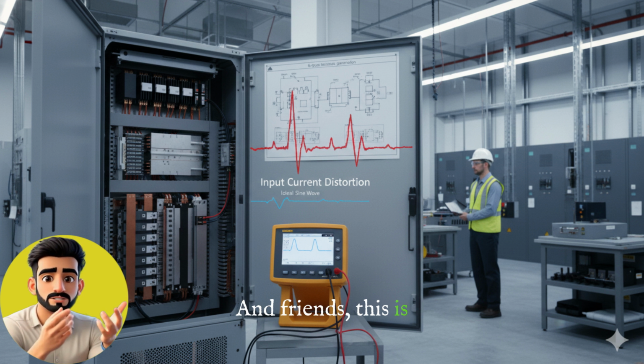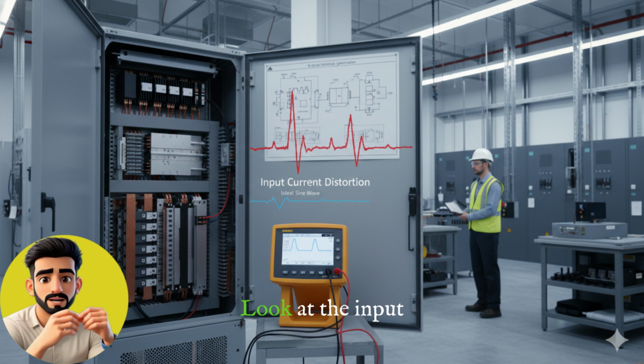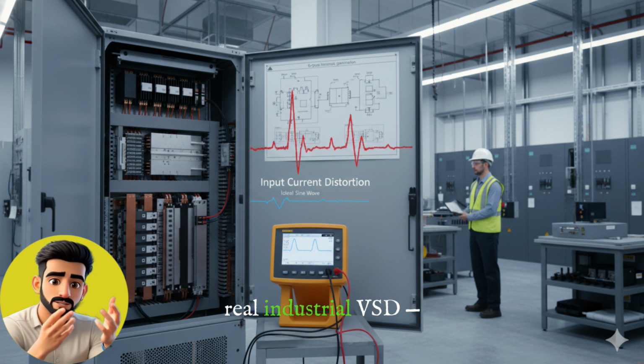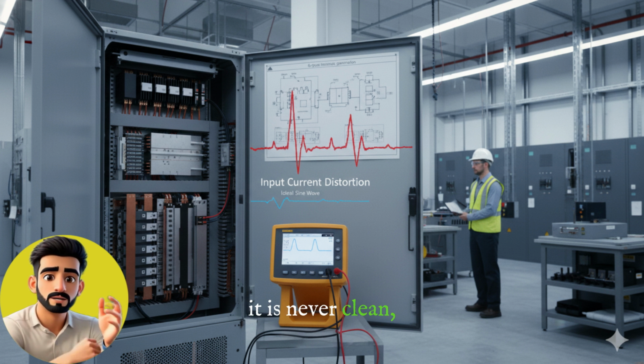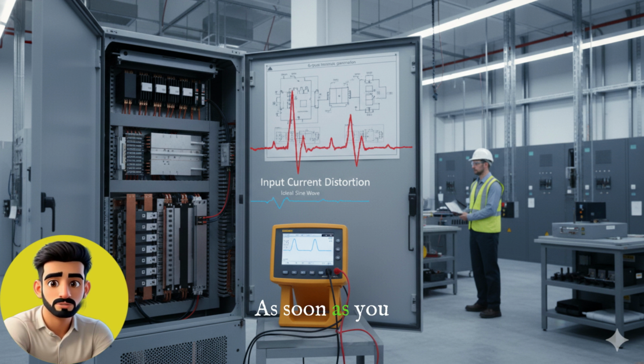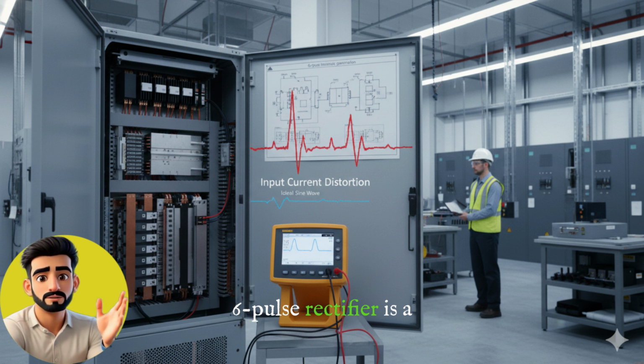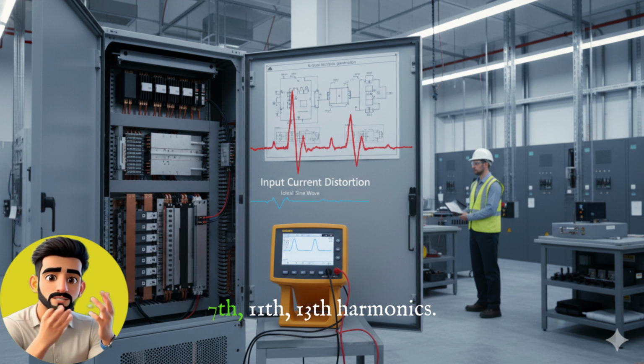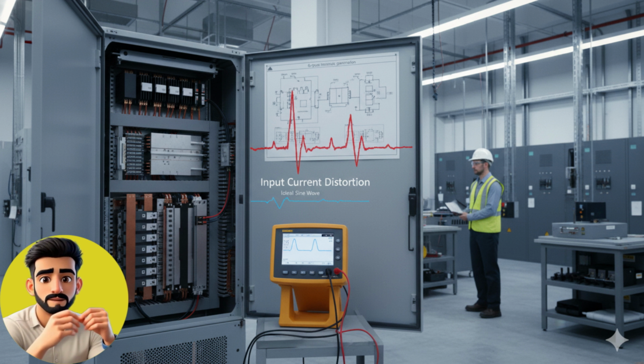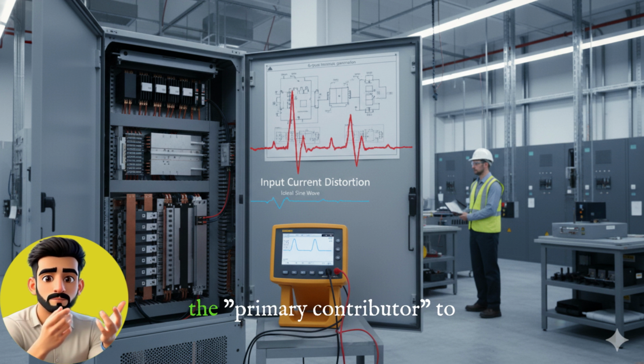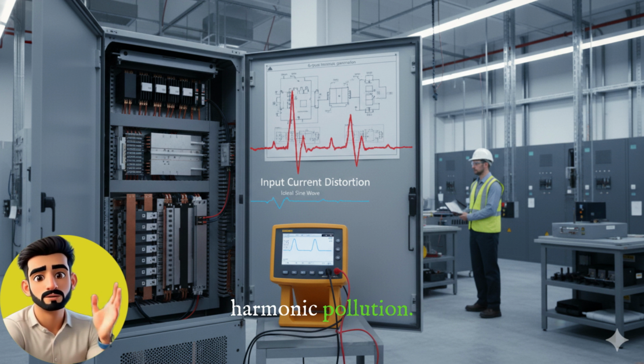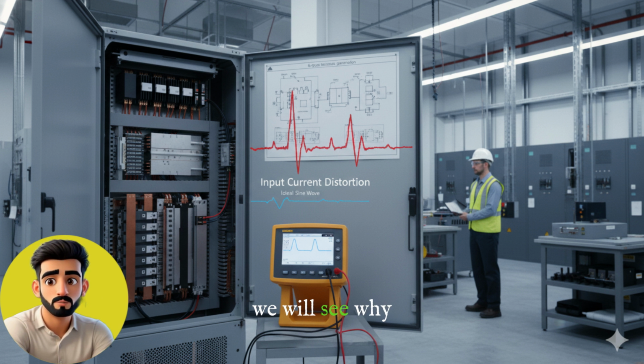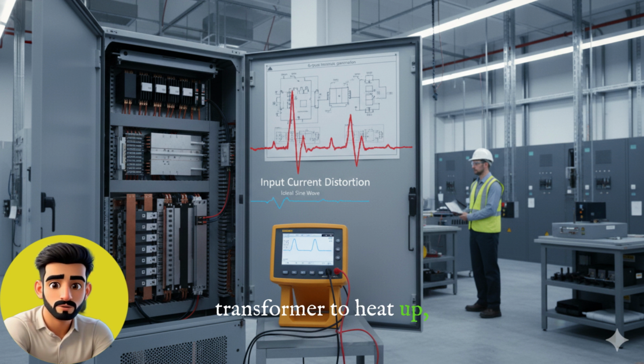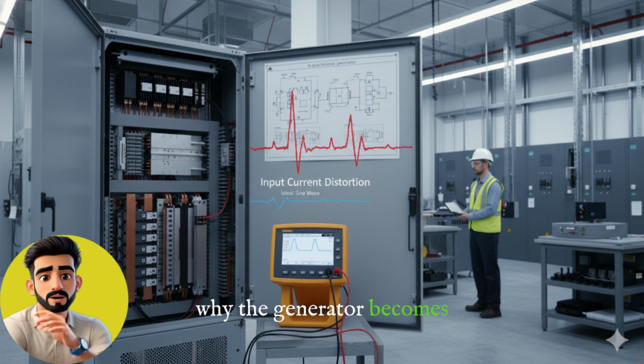And friends, this is not just a theoretical concept. Look at the input current waveform of any real industrial VSD. It is never clean, round, or smooth. As soon as you see the wave, you will immediately understand, yes, the distortion is originating from here. Especially the 6-pulse rectifier is a major source of 5th, 7th, 11th, 13th harmonics. That is why the 6-pulse VSD is considered the primary contributor to harmonic pollution. In the upcoming scenes, we will see why these distortions cause the transformer to heat up, overheat the cables, and why the generator becomes unstable.